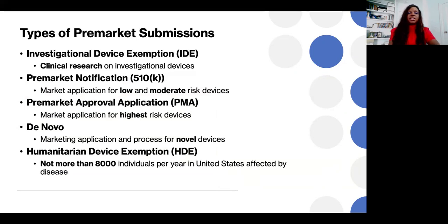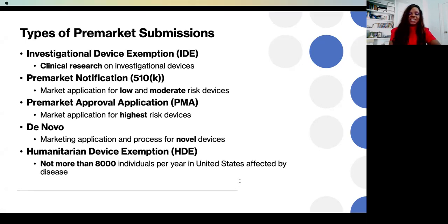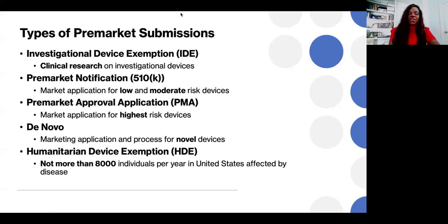Okay, so now we want to talk a little about the different types of pre-market submissions. There are basically 5 main types of pre-market submissions that we would send to the FDA. An investigational device exemption is usually used in clinical research on investigational devices. A pre-market notification, or 510K, is the market application for low and moderate risk devices. A pre-market approval application is a market application for highest risk devices. A de novo application is usually used for a novel device, and when there are just about 8,000 individuals per year in the US that are affected by the disease, then we would have an HDE application sent to the FDA. Next slide, please.